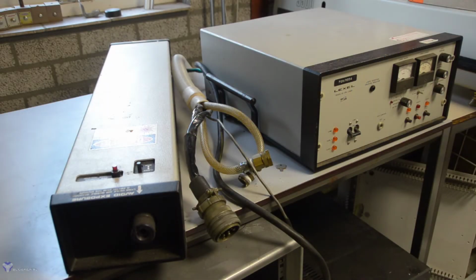Today I want to fire up this old argon laser. It's really an old beast. Argon lasers are really not used anymore, and this unit also has been sitting still for quite some time. It's a Lexel 85 and it should be able to output about 1 watt multi-line, or if you select single laser lines, somewhere between 45 and 400 milliwatts, depending on which line you select. Because as we'll see later, there's a prism selector on the back.